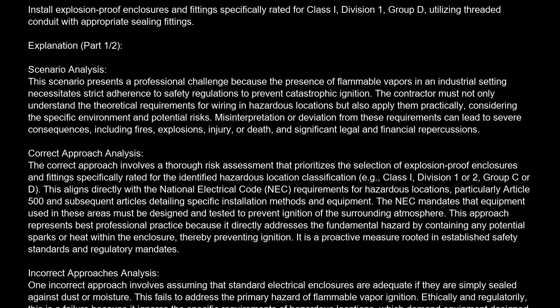The correct approach involves a thorough risk assessment that prioritizes the selection of explosion-proof enclosures and fittings specifically rated for the identified hazardous location classification, e.g., Class I, Division 1 or 2, Group C or D. This aligns directly with the National Electrical Code, NEC, requirements for hazardous locations, particularly Article 500 and subsequent articles detailing specific installation methods and equipment.